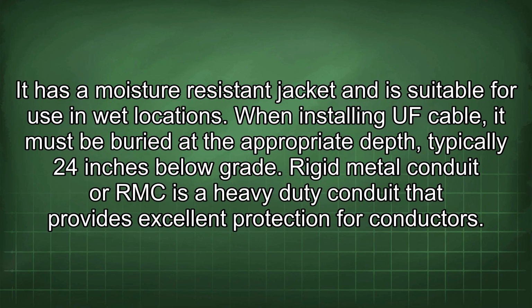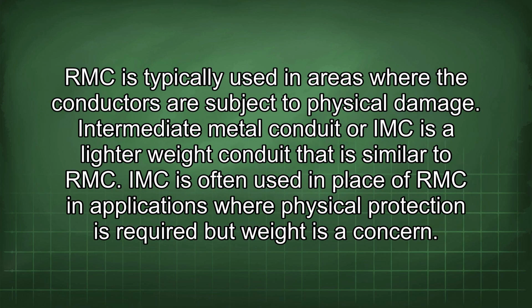Rigid metal conduit or RMC is a heavy-duty conduit that provides excellent protection for conductors. RMC is typically used in areas where the conductors are subject to physical damage. Intermediate metal conduit or IMC is a lighter weight conduit that is similar to RMC. IMC is often used in place of RMC in applications where physical protection is required but weight is a concern.